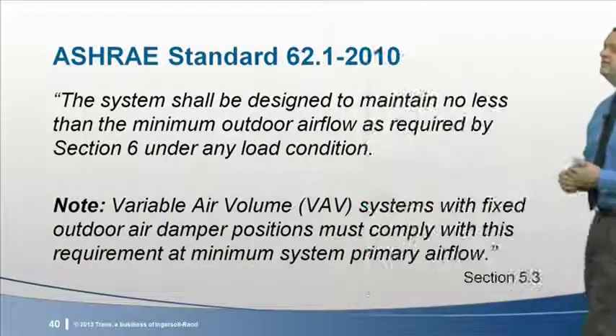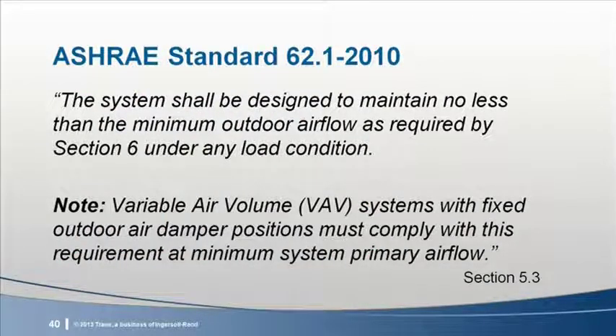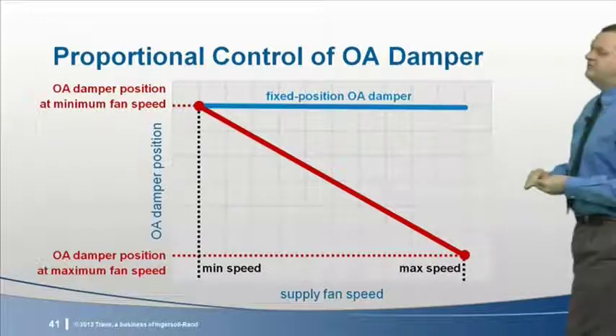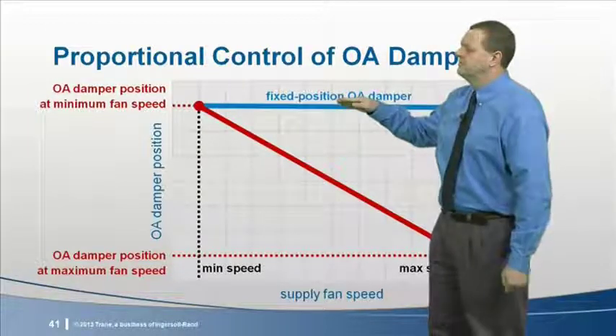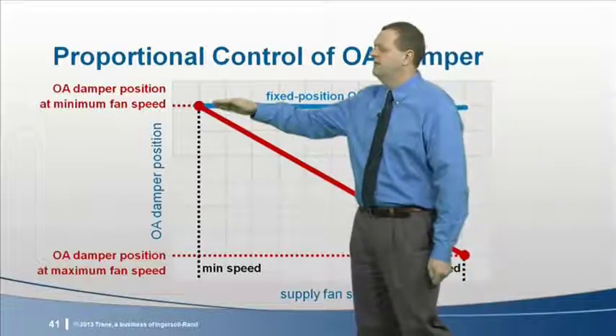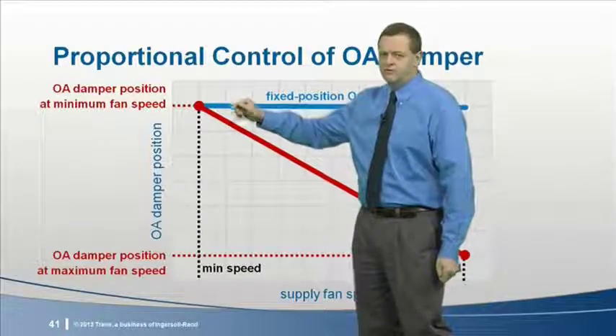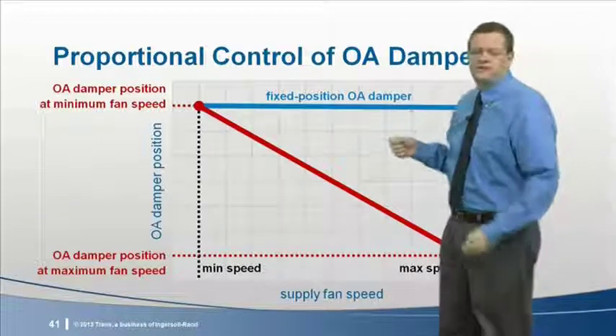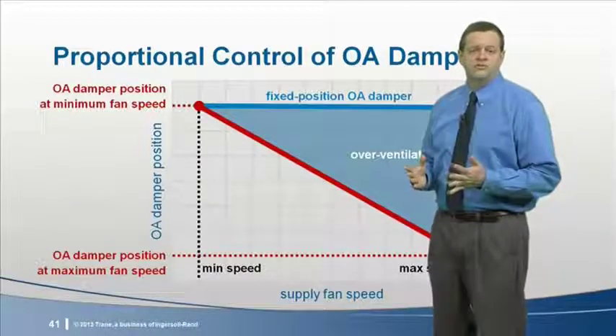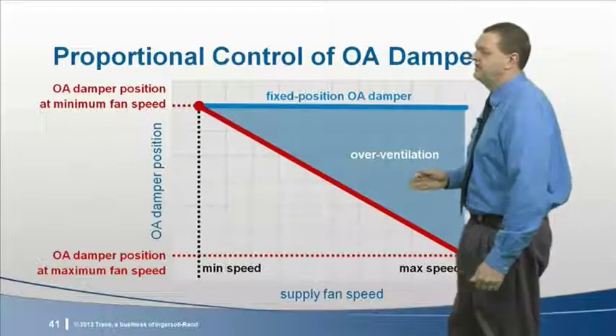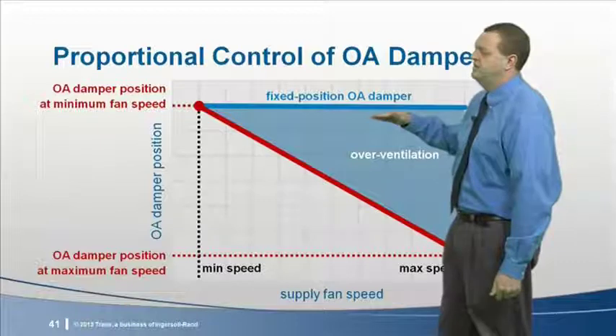That's because Standard 62.1 requires that a system maintain the required minimum outdoor airflow under any load condition. And it clarifies that if a variable airflow system uses a fixed position outdoor air damper, you need to be sure that it complies at the minimum system airflow. This means you need to fix the damper position up here so that you bring in the minimum required outdoor airflow when the fan is operating at minimum speed. Of course, this results in overventilating at all these other fan speeds. So a proportional damper control strategy results in significantly less overventilation than fixing the damper position up here for worst case.